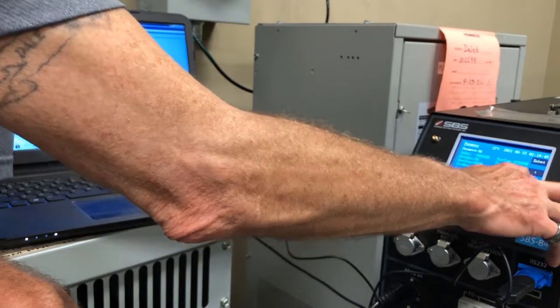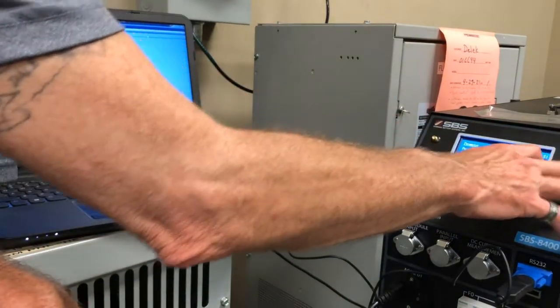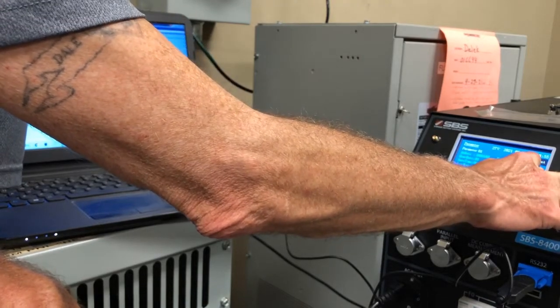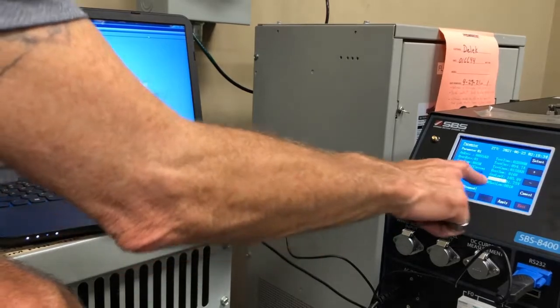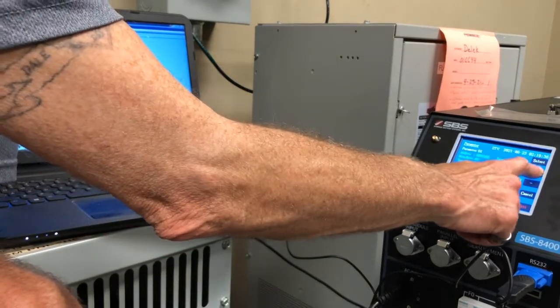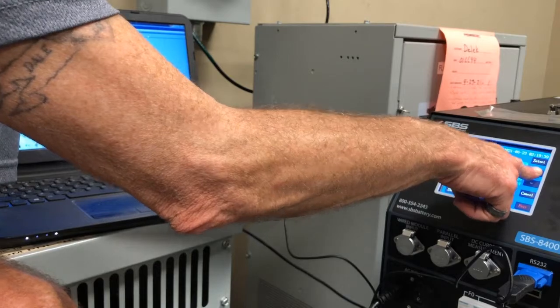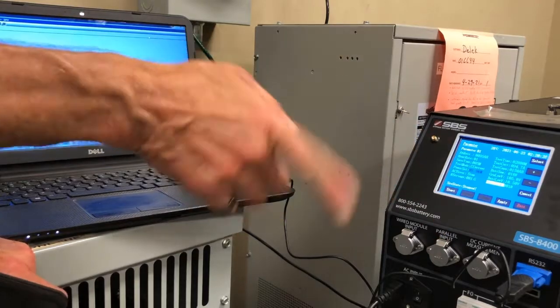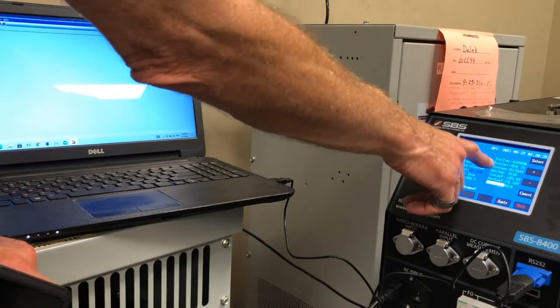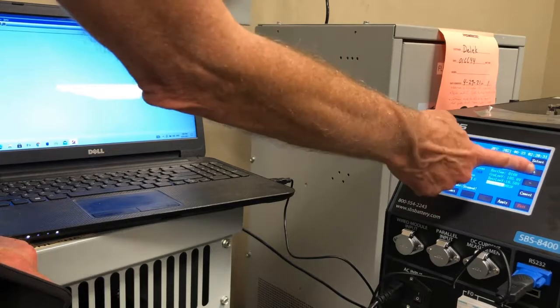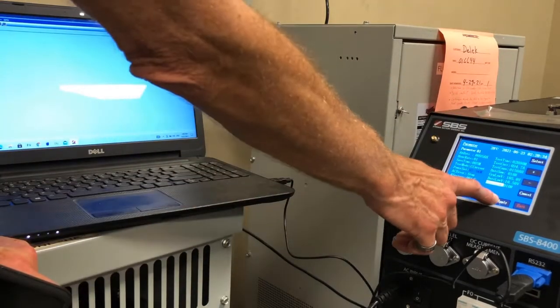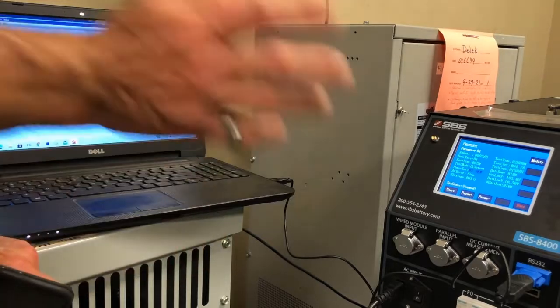Right. We're testing 10 12 volt block batteries. Group low voltage is going to be 105.0. Low battery voltage using the modules would be 10.5. And because we're not using the wireless modules, my number of battery lows has to equal my battery sum. Okay. So we set that to 10. We hit apply. That saves that as preset number 1.